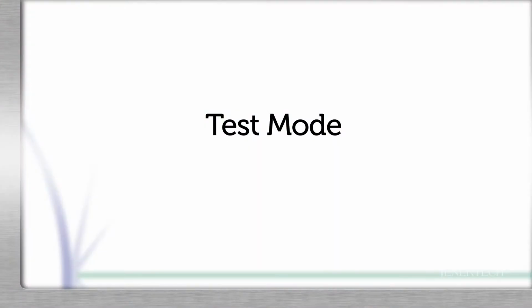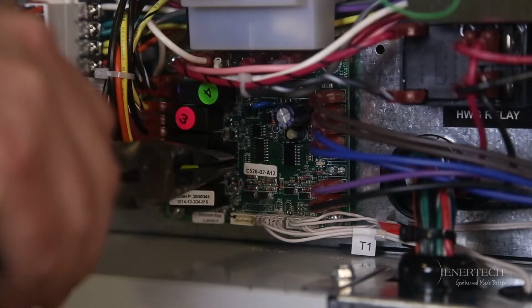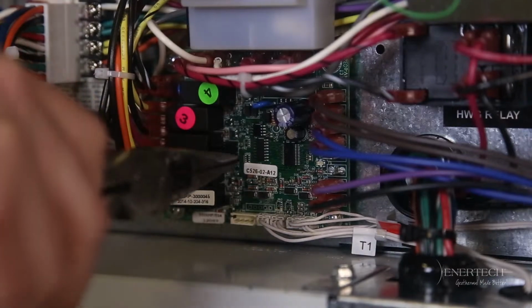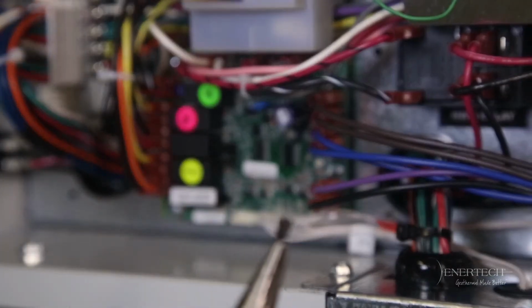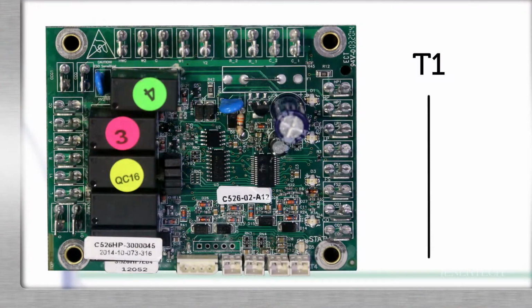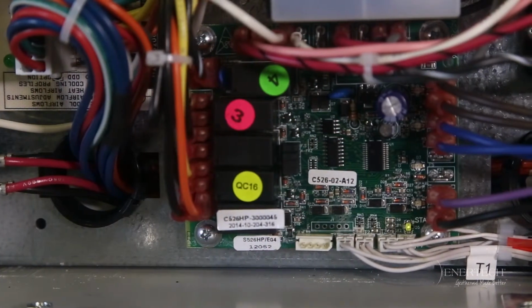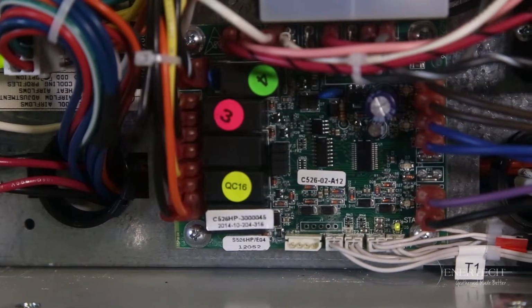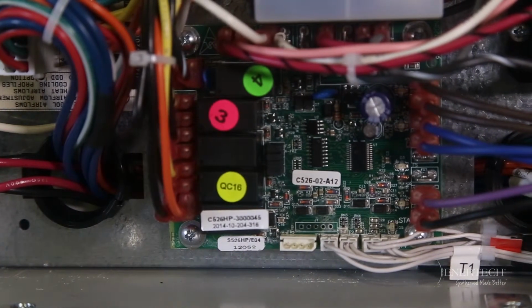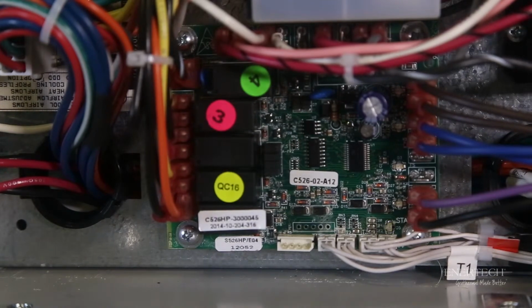When the test jumper is installed, the board operates in the normal mode. When the jumper is removed, the board operates in test mode, which speeds up all delays for easier troubleshooting. While in the test mode, the T1 and T4 sensors will be checked for proper location based on temperature. Sensors are swapped if T1 is greater than T4 in cooling, or T1 is less than T4 in heating. This fault will only show up in the test mode.